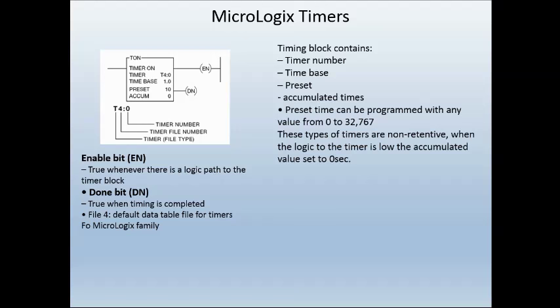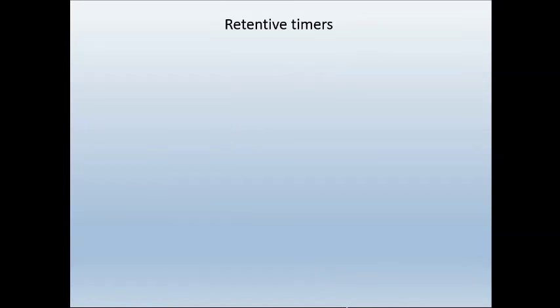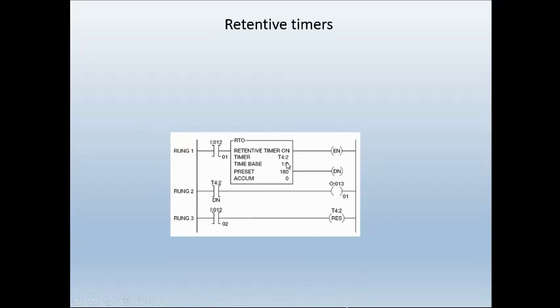Some bits on our timer that we can use in our logic: the enable bit is true whenever the logic path in front of the timer is true. The done bit is only true when the preset and the accumulated value are the same — so when I set the preset to 10 seconds, when the accumulated value reaches 10 seconds, the timer becomes done. File 4 is the default data table for timers. The first word stores the enable bit, the timer timing bit — which is true whenever the timer is timing — and the done bit. The second word stores the preset value, and the third word stores the accumulated value.